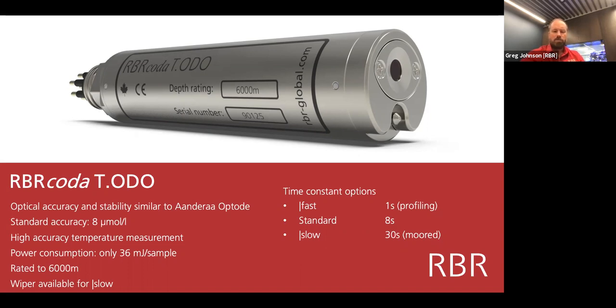However, when you look at the differences and try to compare against the Aanderaa optode, you'll see that the Aanderaa offers two different time constants. One is what they call standard and we call slow, a 30-second time constant using a foil that's protected by a Teflon cover. The second is the 8-second time constant, what they call fast, but we just call our standard one. In addition to that, we have a fast foil that is really fast for oxygen measurements with a 1-second time constant, typically used in profiling applications.